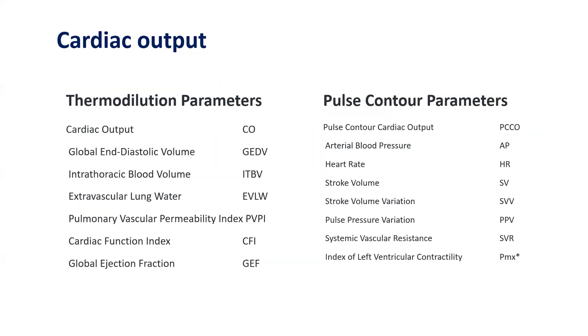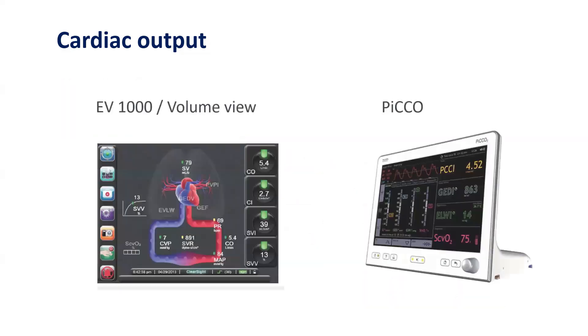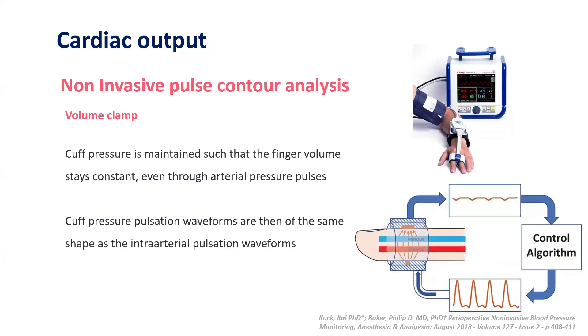Different parameters can be measured by these two techniques, and when thermodilution and pulse contour analysis are combined, better results are obtained. Most modern cardiac output monitoring devices — including the VolumeView and PiCCO — combine thermodilution and pulse contour analysis. Non-invasive pulse contour analysis using volume clamp is also being explored, where cuff pressure is maintained so that finger volume stays constant through the arterial pulse, and the cuff pressure pulsation waveforms match intra-arterial pulsation waveforms.